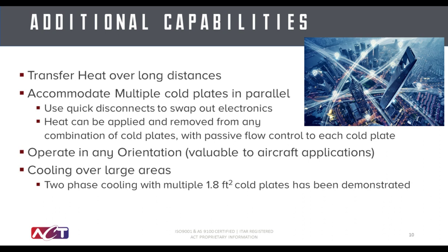Some additional capabilities for a pumped two-phase system include the ability to transfer heat over long distances. You can pump the refrigerant through a cold plate, and then many feet of tubing later, you can dissipate that energy to a condenser. That allows remote cooling for components in tight packages. We mentioned you can accommodate multiple cold plates in parallel, which is of benefit to a number of different systems, and it can operate in any orientation, which is valuable for aircraft applications or any application where your hot components may be articulating. It's also possible to dissipate heat over large areas with pumped two-phase cooling. At Advanced Cooling Technology, we've demonstrated cold plates upwards of 1.8 square feet in area.